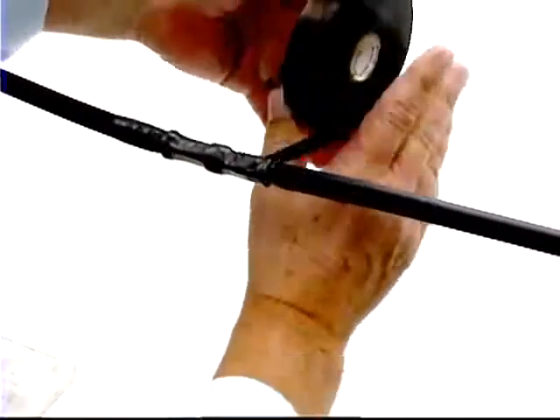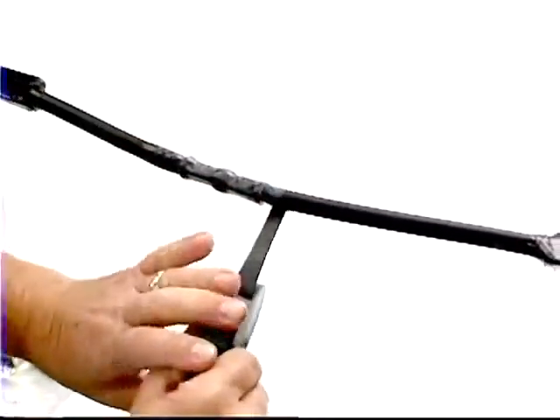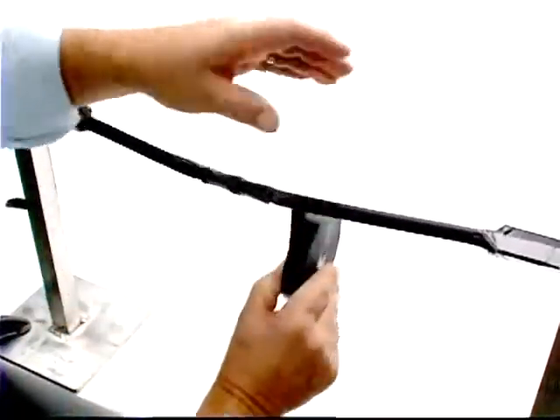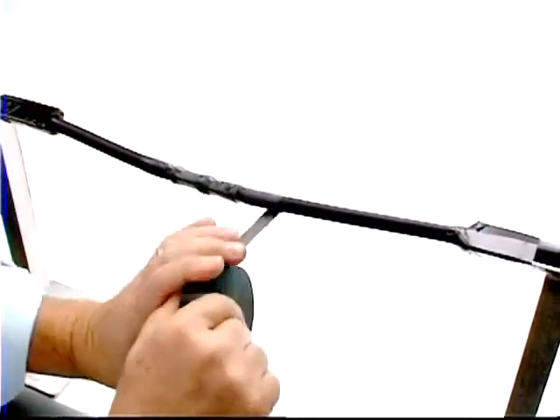Wrap from the edge of the connector past the beginning of the cable jacket on one side. Hold the tape tightly and pass it from one hand to the other while pulling just enough that you feel the tape stretching. This will help you provide a consistently tight wrap.